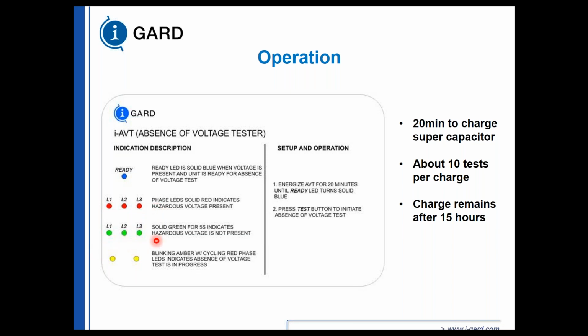3 green LEDs means there is an absence of voltage on the bus, which means it is safe to enter and contact and perform work on the area that this device is connected to. The blinking amber or yellow lights indicate that it is undergoing a test. The test is in progress, and we'll get more to the test later. It takes about 20 minutes to charge the supercapacitor. Contrary to some of the other devices that are out there, they use batteries. We use a capacitor. You get about 10 tests per charge, and the charge can remain for up to 15 hours.